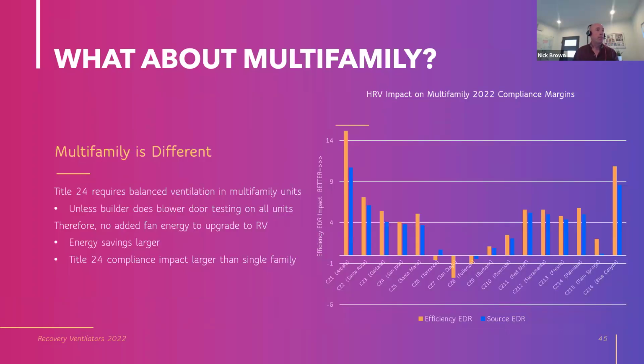design. What about multifamily? We've been talking mostly about single family so far. Well, interesting. The code, first of all, is different for multifamily indoor air quality. Title 24, the 22 code, requires balanced ventilation in multifamily units unless the builder does blower door testing on all the units, in which case they can continue using exhaust-only ventilation. This was new for the 22 code. We didn't know what to expect.